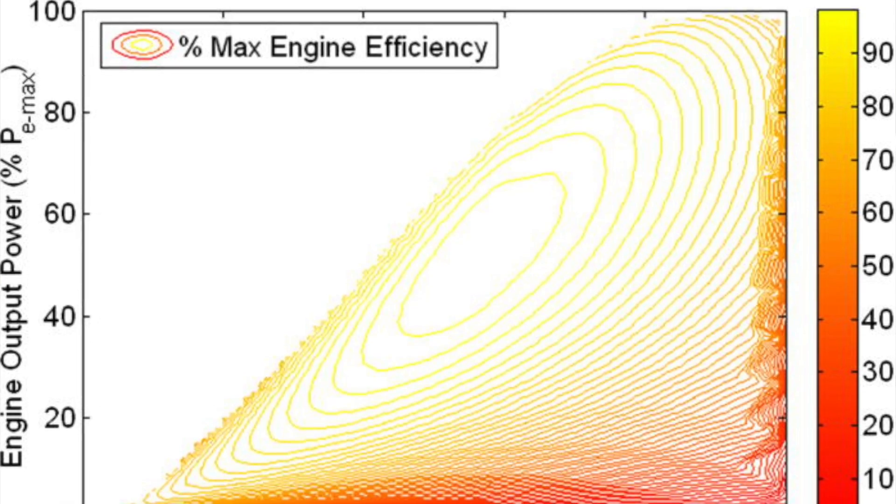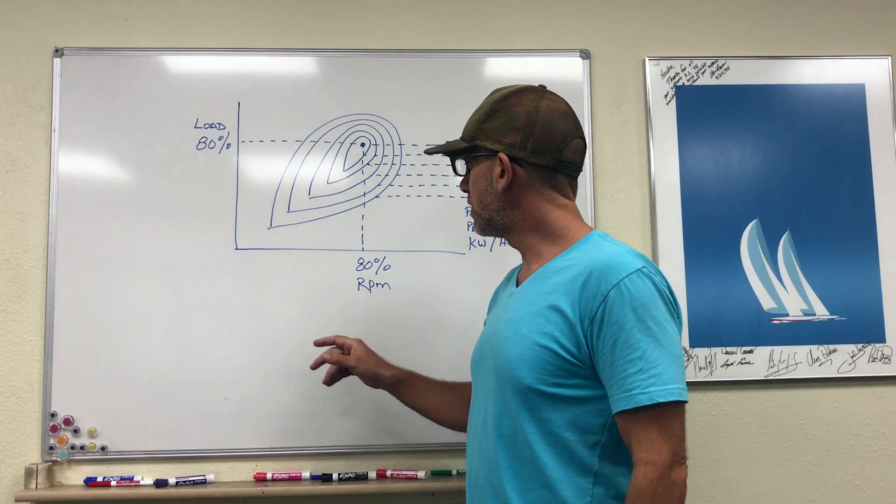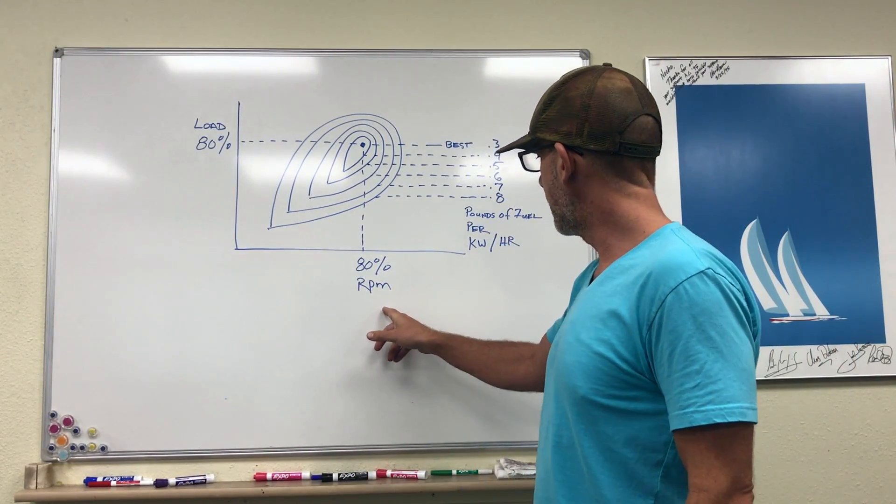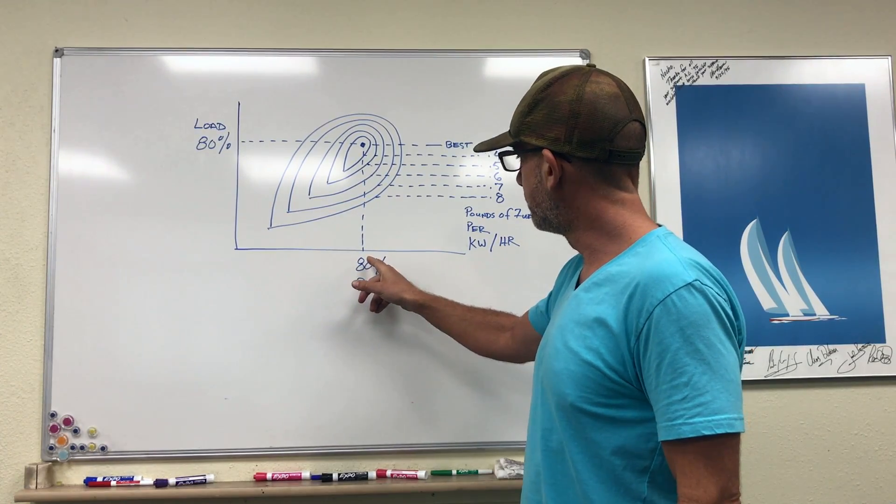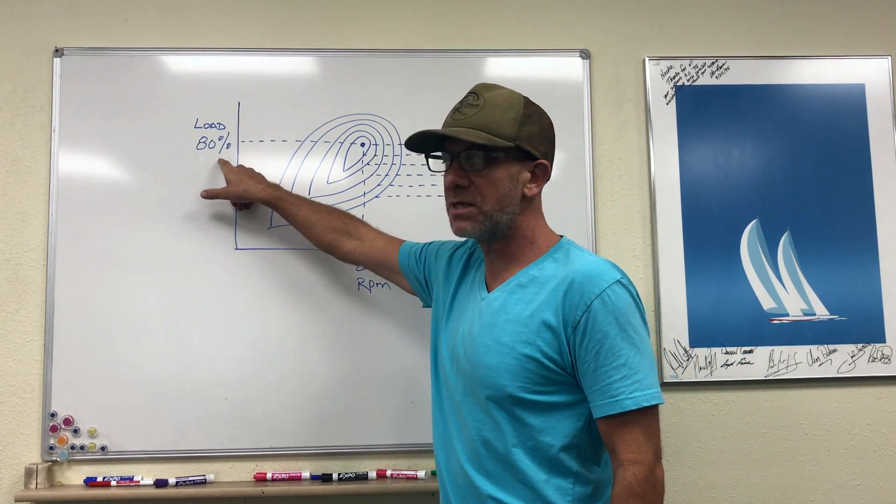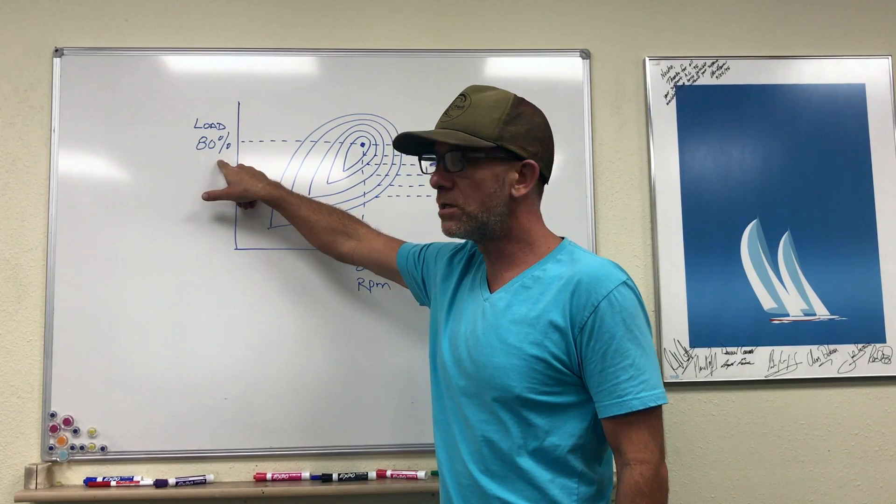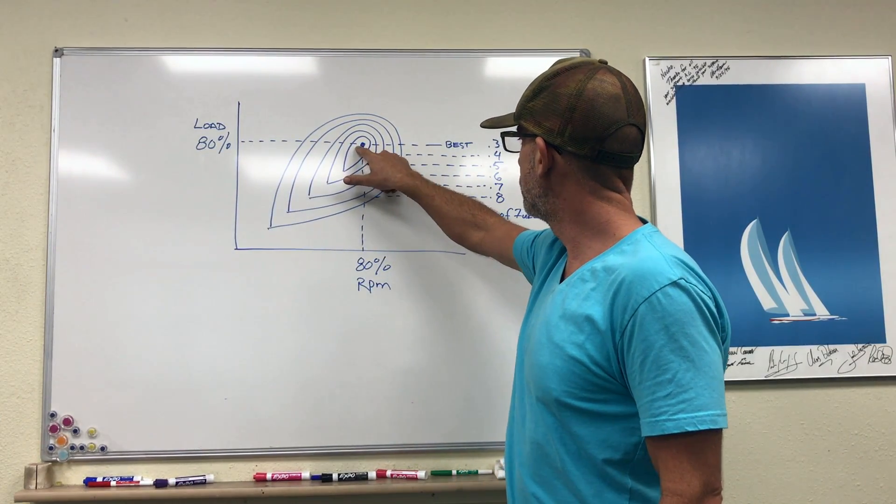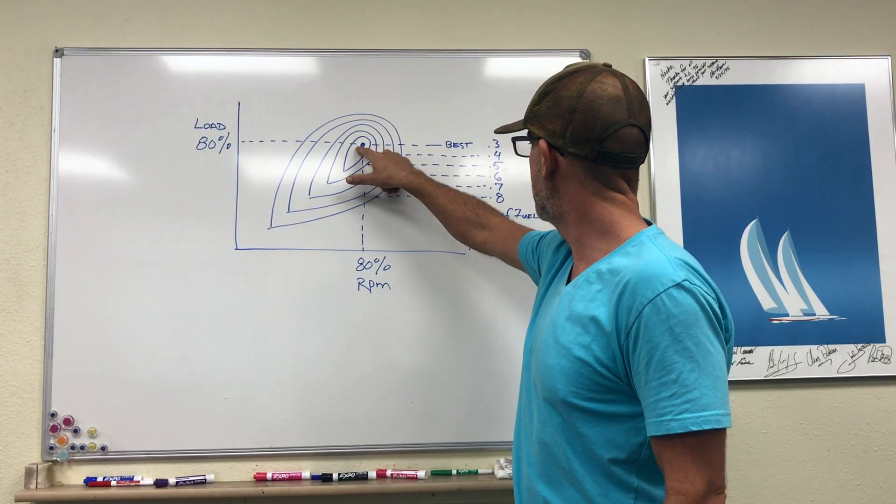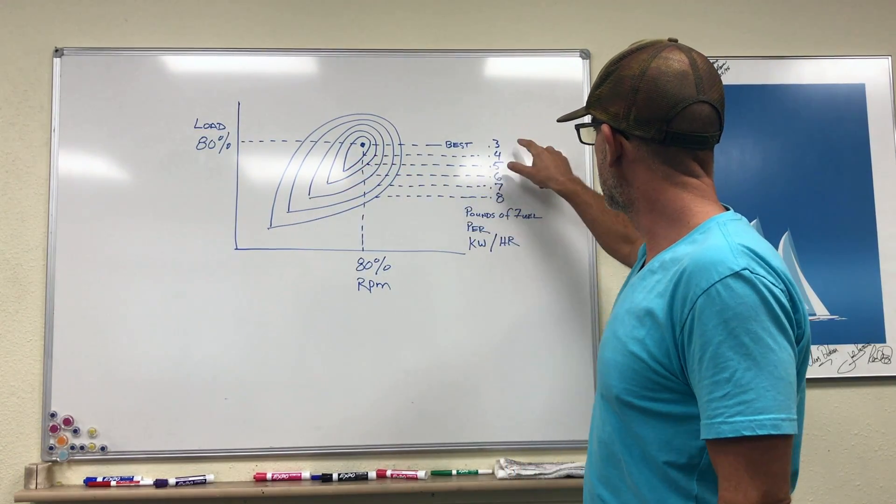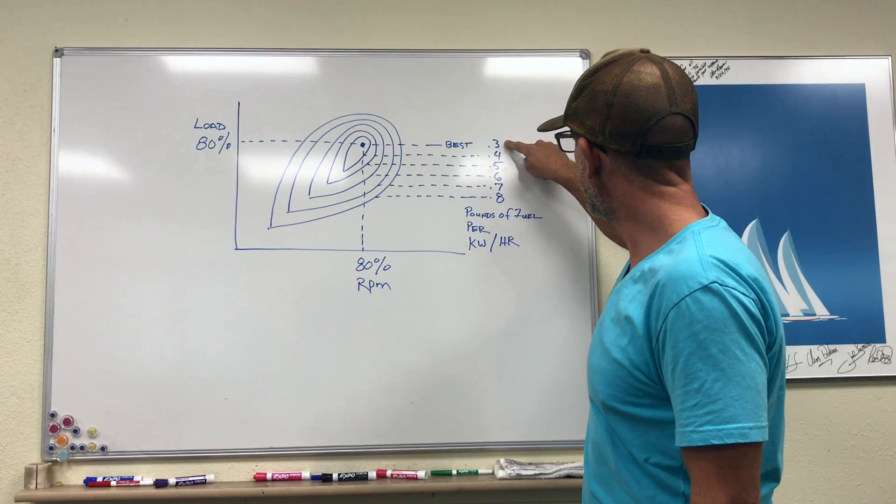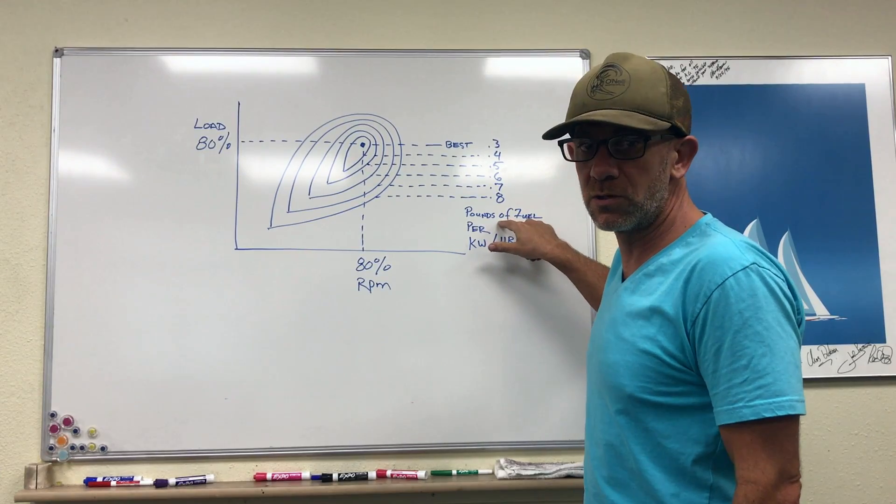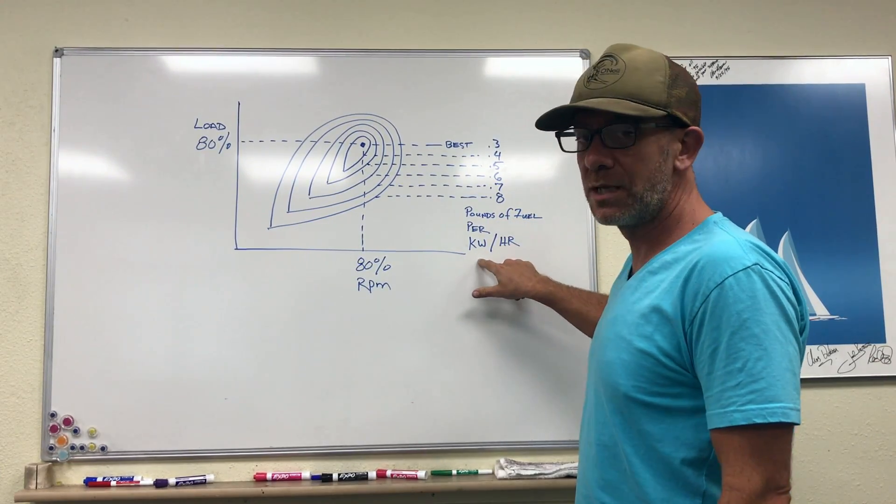So what this shows is that when the diesel engine is running at roughly 80% of its RPM and it has approximately an 80% load, that is going to achieve your very best efficiency. And in this case, this is 0.3 pounds of fuel per kilowatt hour.